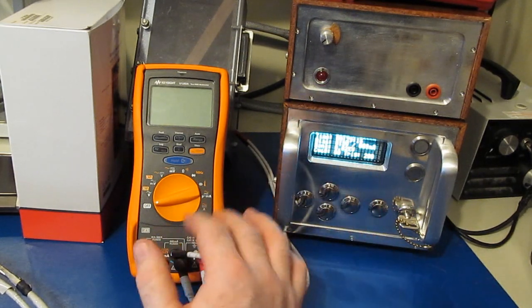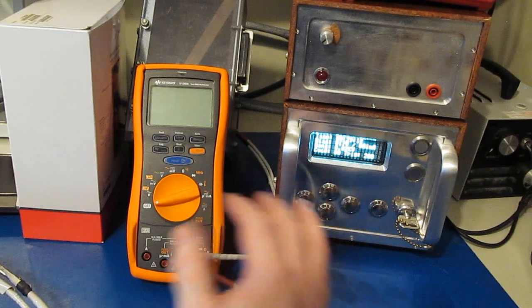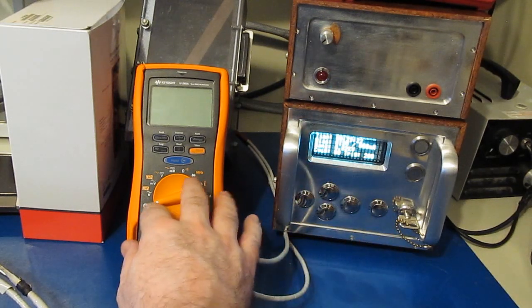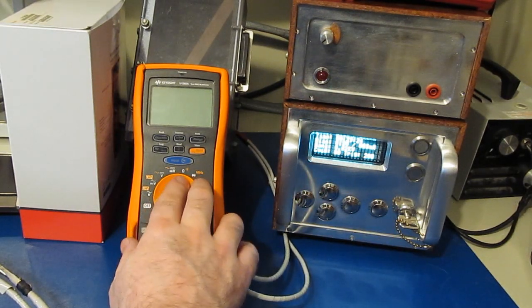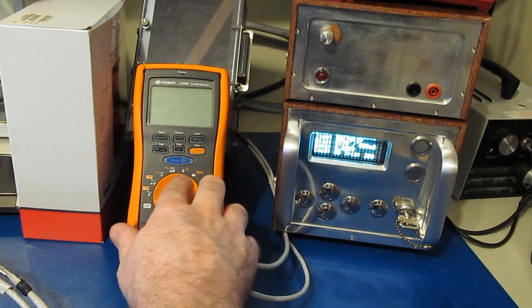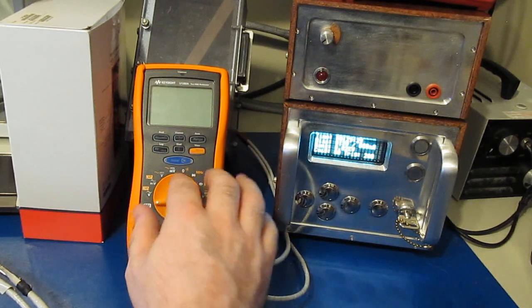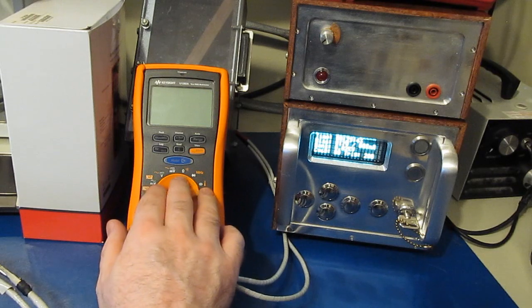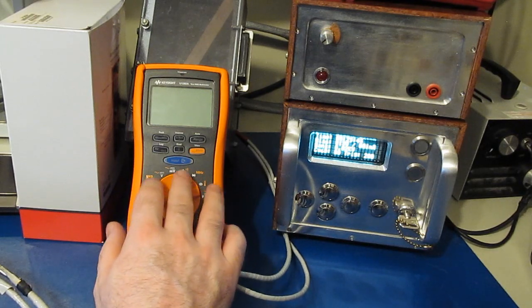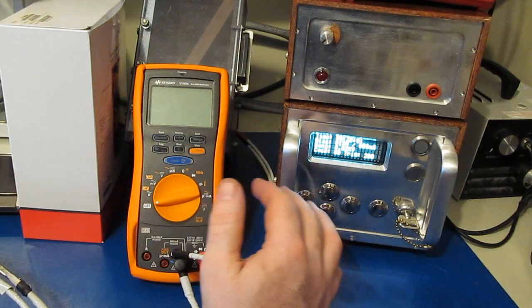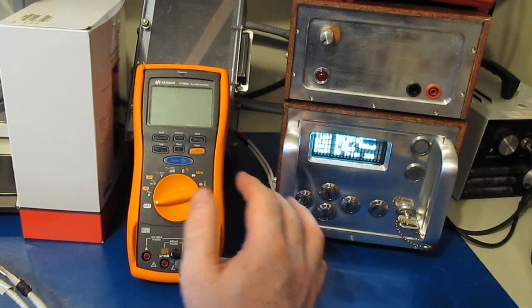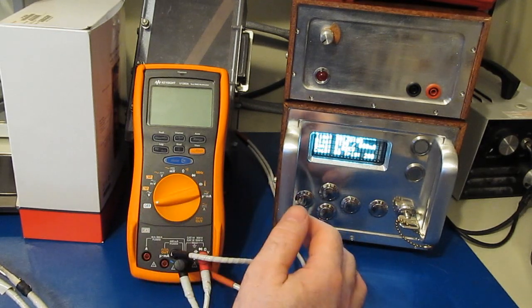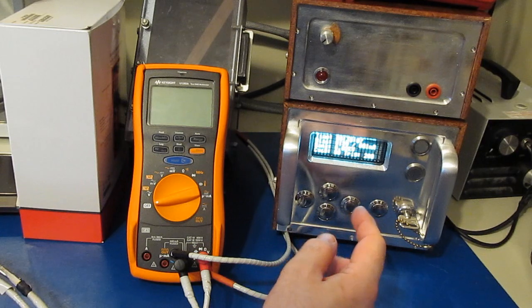So the only time that the meter is going to absorb any energy is if it starts to break down, or in the case of, let's say, the meter in the resistance mode, it's going to engage that high-speed, low-voltage clamp, and then some of it is going to be dissipated across that input resistor as well as the PTC. At these levels now we should start to see the gas discharge tube firing. So let's see if it changes the wave shape at all.